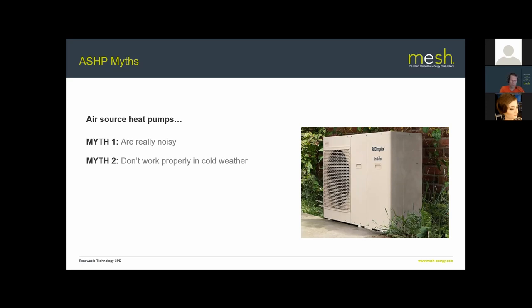Myth two: air source heat pumps don't work properly in cold weather. It's true that output drops with ambient temperature, but if you size the heat pump correctly it will provide the heat required throughout the year. Most air source heat pumps are designed to work down to around minus 25°C, which is absolutely fine for anywhere in the UK. In northern Scandinavia with very harsh conditions, you might consider some backup heating — which is why ground source is more common there.